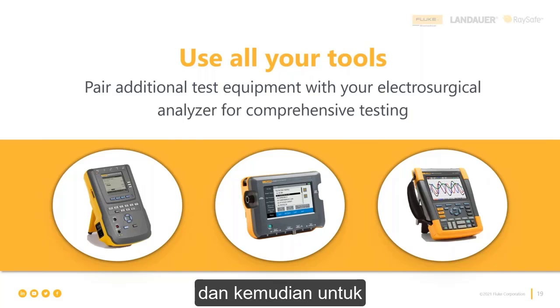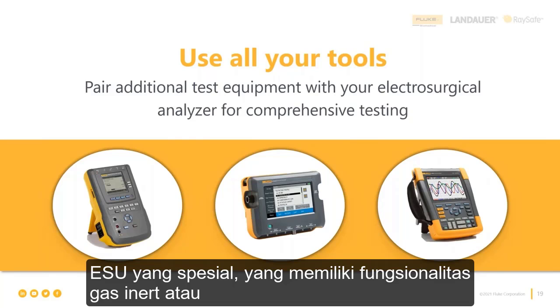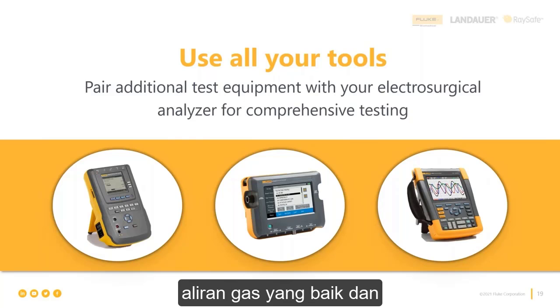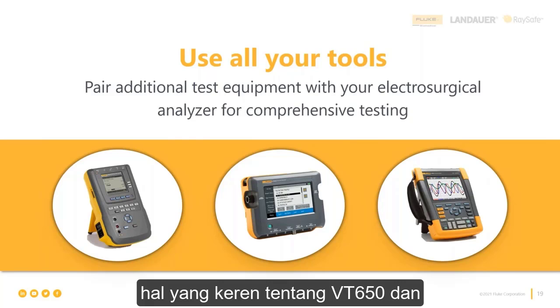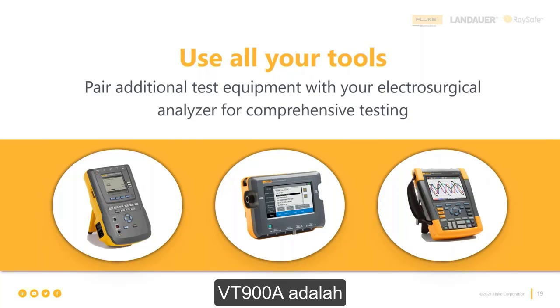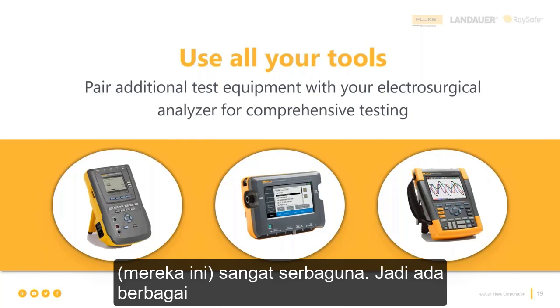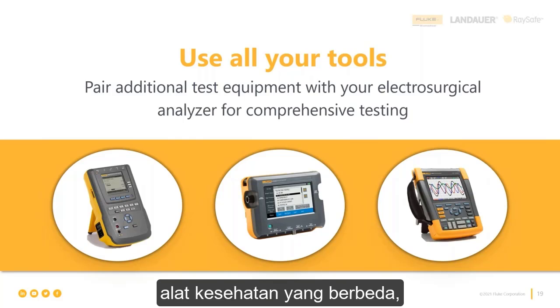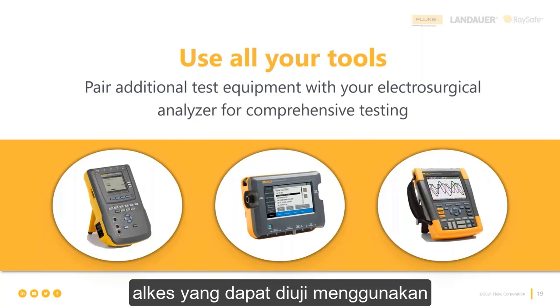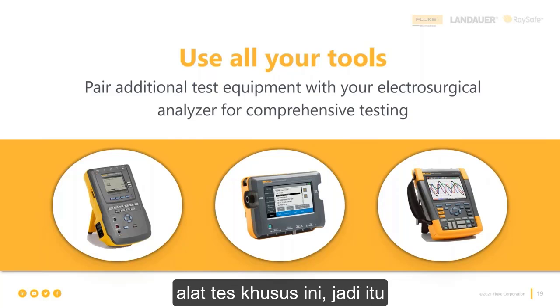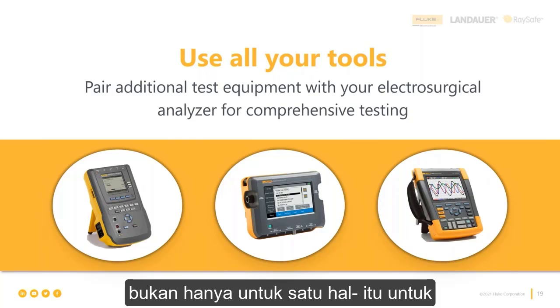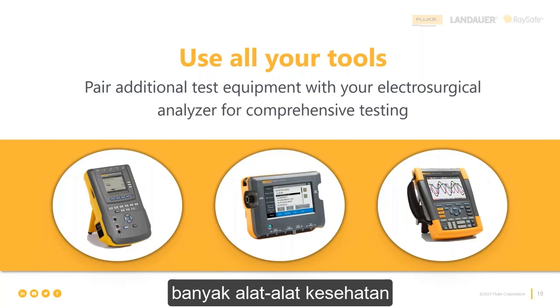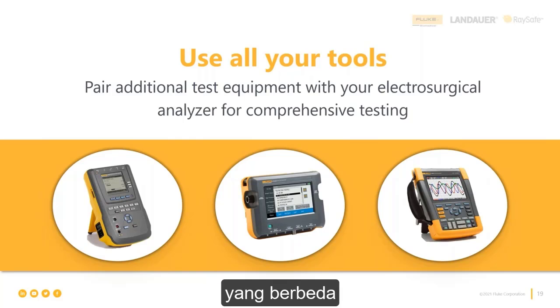And then for those special ESUs that have this inert gas or argon gas functionality, a good gas flow and pressure analyzer. The neat thing about the VT 650 and VT 900A is that they're very versatile. There are a host of different medical gas flow and pressure devices that can be tested using this particular test instrument. So it's not just for one thing, it's for a lot of different medical devices.